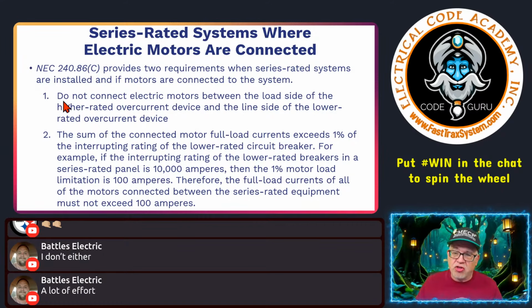Here's what it says in 240.86(C). Do not connect electric motors between the load side of the higher rated overcurrent device and the line side of a lower rated overcurrent device. So don't put the motor in between. It makes sense. Obviously there's an application where that may happen, but it says don't do that. And then it says the sum of the connected motors' full load current, remember FLC from 430.248, 249, 250, whatever you're dealing with, exceeds 1% of the interrupting rating of the lower rated circuit breaker.